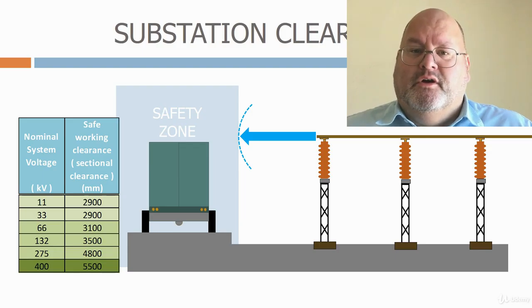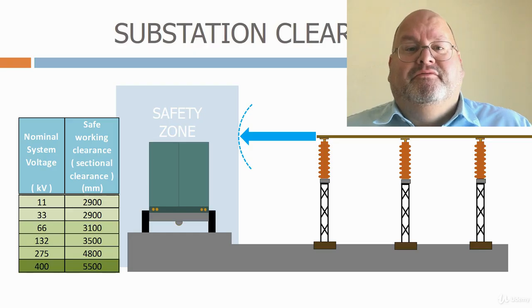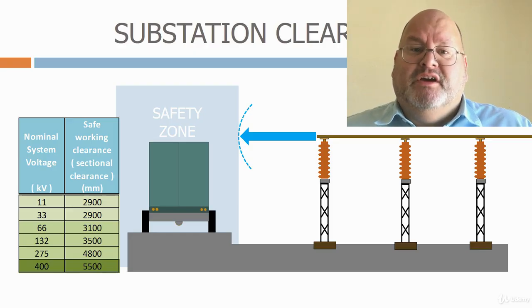You will find, as you work around the world, that phase-to-ground and phase-to-phase clearances are pretty similar whichever utility you choose to work with. However, the definition of sectional clearances and how they are applied varies widely from country to country. Some utilities use the simple approach we've used here, where we have a sectional clearance for all conditions. Other utilities have defined different horizontal and vertical sectional clearances, as well as separate minimum distances for fence lines, roadways, and bus bar heights, so it's critical that you read the utility's standard before commencing any substation layout design.